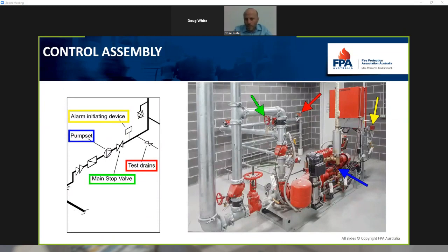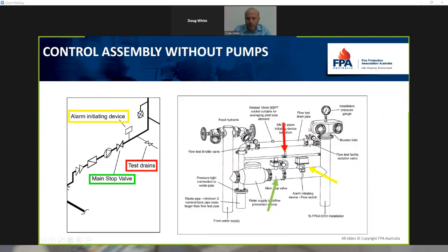Where you require a pump set, you can get away with installing the alarm initiating devices, test drains, main stop valves and whatnot at the pump set. You can see with those arrows where they typically would be installed on the pump set. So it should be pretty familiar. Where there isn't a pump set, you can connect them down at the booster inlet.